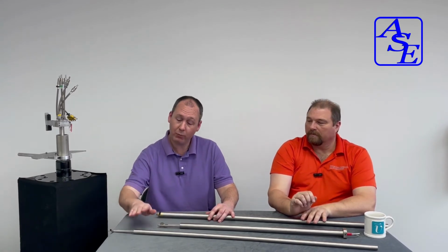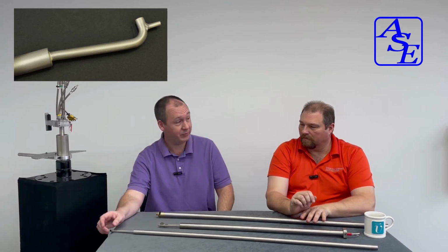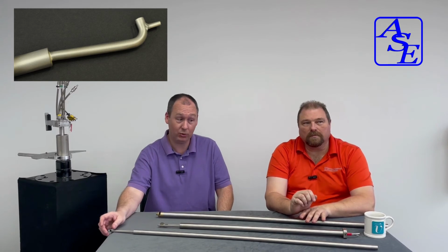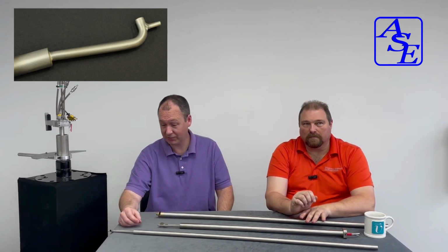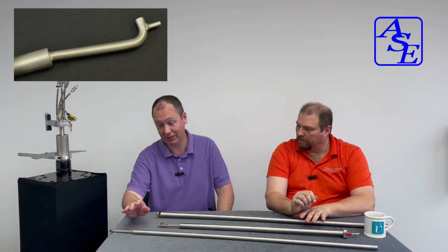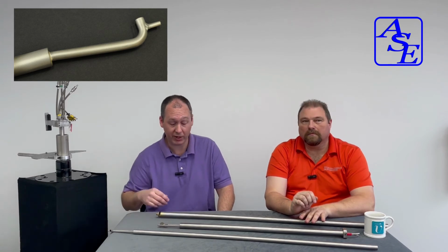Okay. The probe we've designed here is very similar in function. It just has a little bit of a different nozzle. So what we've found is, with a smaller nozzle, you can get away with a little less vacuum, so your setup's a little simpler. And also, we've just found through extensive testing that the results are a lot more repeatable and representative when you use the smaller circular nozzle.